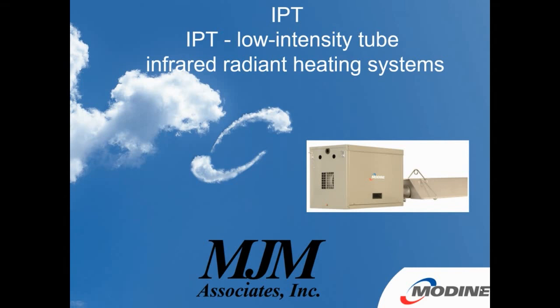So the next thing we're going to go to is IBTs. This is the big magic heat system. It's really funny because with infrared tubing heat, if you stop and look at it, it's not that efficient. You've got a 4-inch tube that you fire into and it blows out directly out the end. There's no real heat exchange. If you actually looked at the AFUE rating, it could be as low as 60%. But the effective heat, a whole different category, is how many BTUs we're getting to the floor. It's infrared.